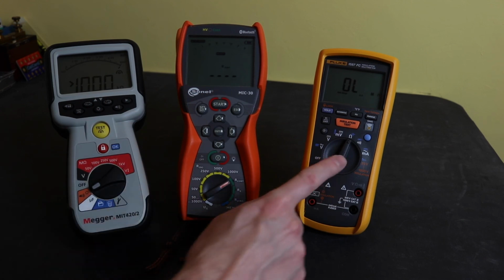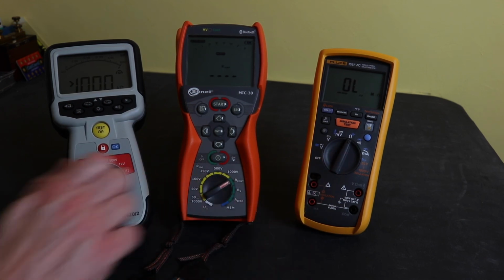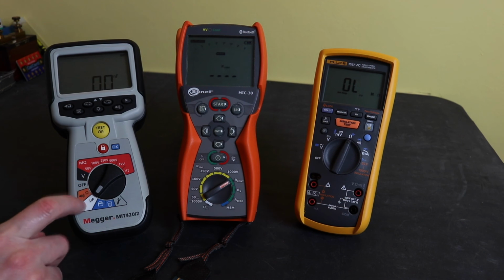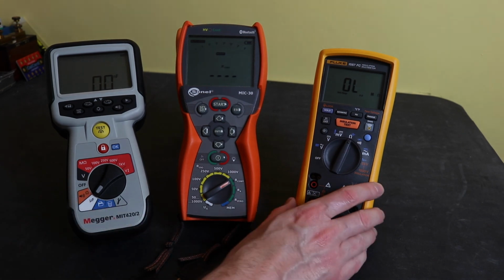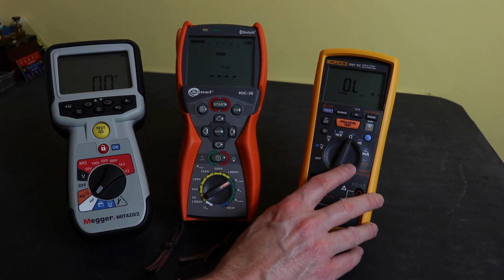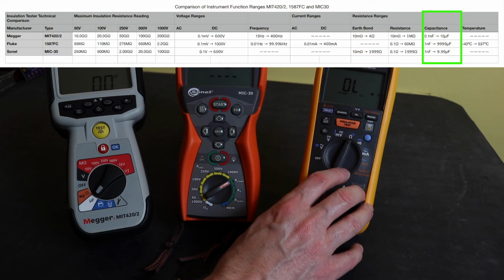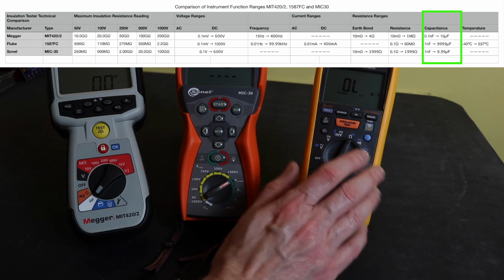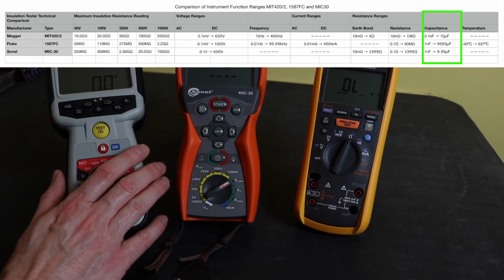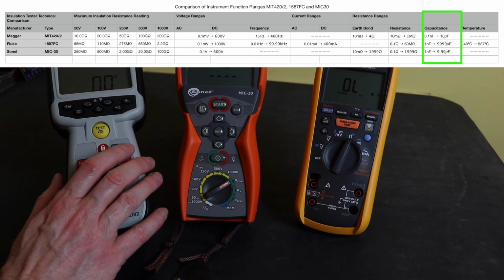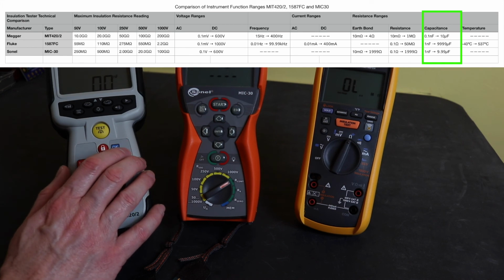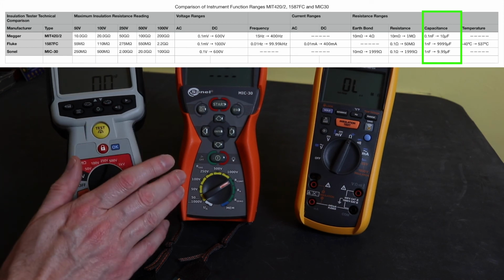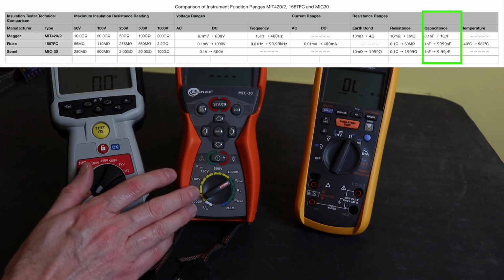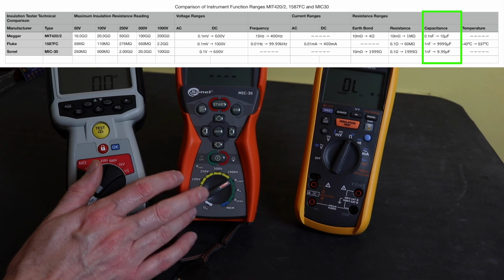Flicking back one, you move on to capacitance. That's one position round on the Megger. Capacitance for the Fluke, you will measure from 1 nanofarad up to 10 millifarads, so a very, very wide range there. For the Megger, you will go from 0.1 nanofarads to 10 microfarads. Now the Sonel does have a capacitance function. It measures from 1 nanofarad up to 9.9 microfarads.